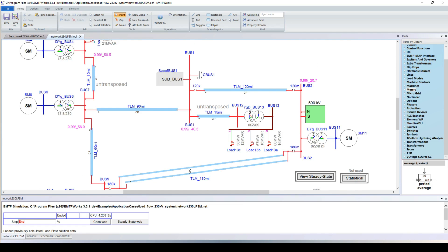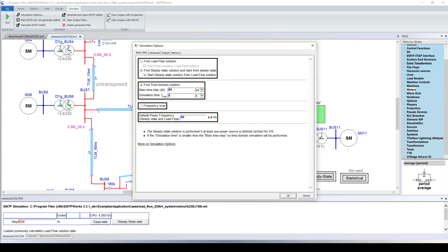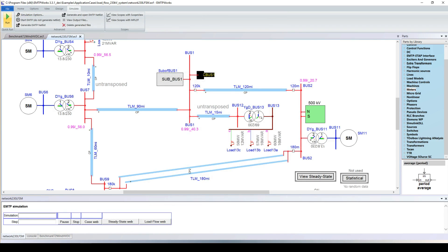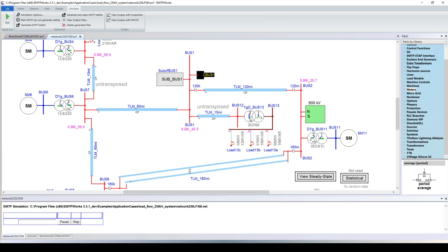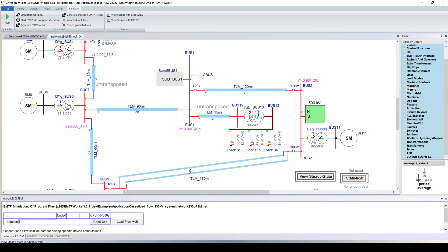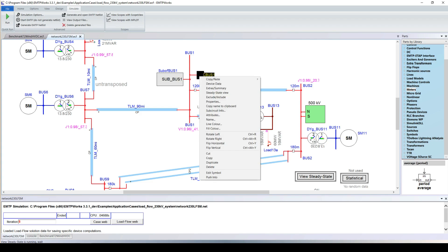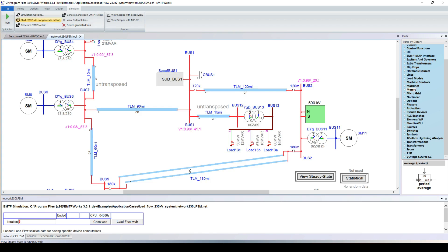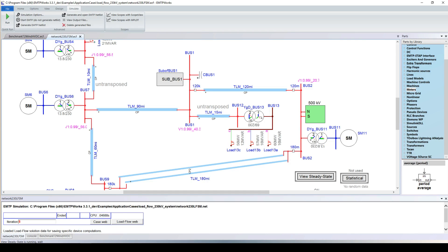Let's say I want to see the voltage on the network without the capacitor bank. I exclude the capacitor bank, go into the simulation options, and run the load flow for this new condition. We can see that at bus 1 we have a voltage of 0.96 PU, which is really the limit. Adding back the capacitor bank and running the load flow again gives 0.99 PU, so the capacitor bank is properly sized.